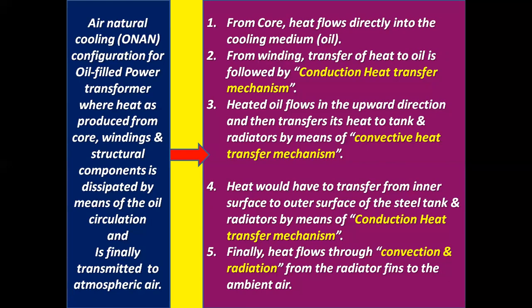Number 1, from the core, heat flows directly into the cooling medium, that is oil. Number 2, from the winding, heat transfer to oil follows the conduction heat transfer mechanism. Number 3, heated oil flows in the upward direction and then transfers its heat to the tank and radiators by means of the convective heat transfer mechanism. Number 4, heat transfers from the inner surface to the outer surface of the steel tank and radiators by means of the conduction heat transfer mechanism. Number 5, finally, heat flows through convection and radiation from the radiator fins to the ambient air. These 5 points are to be noted.